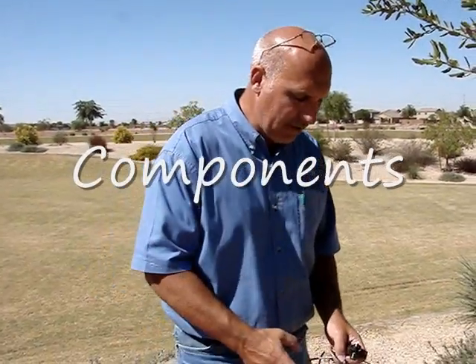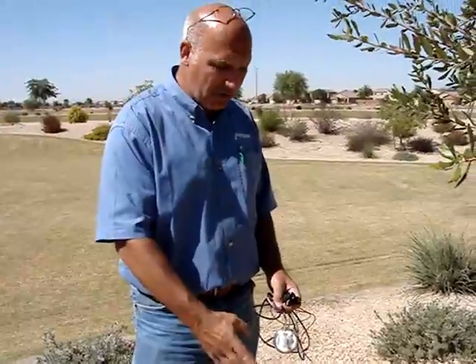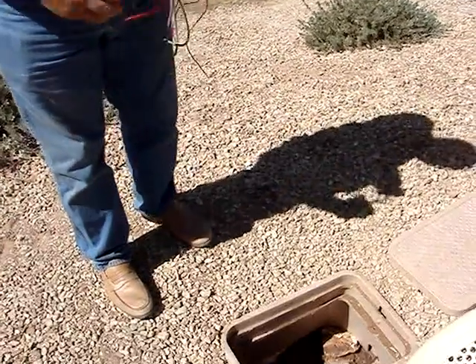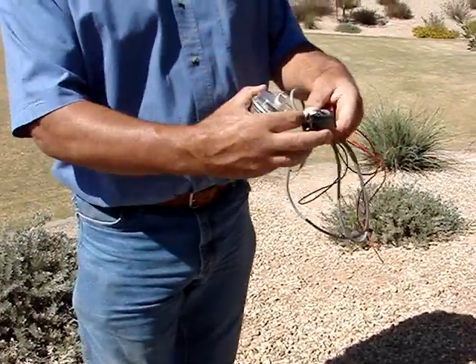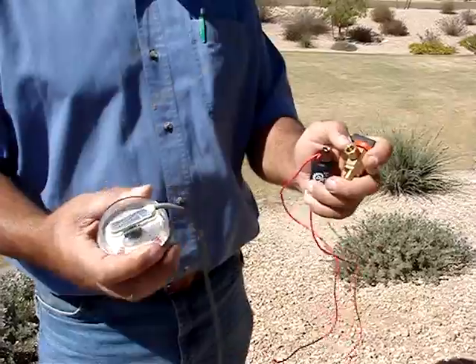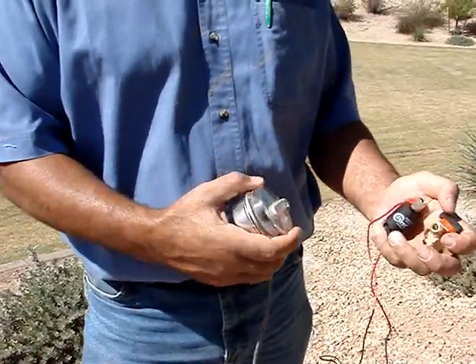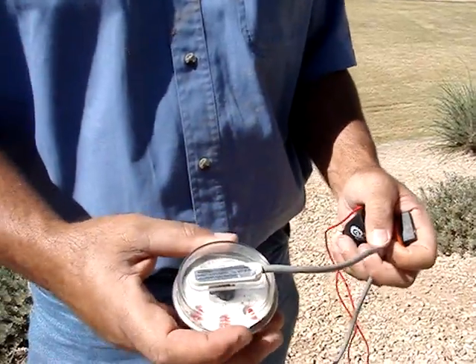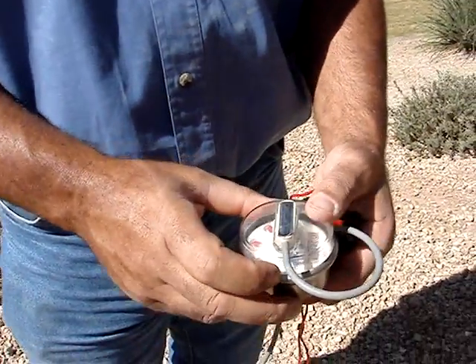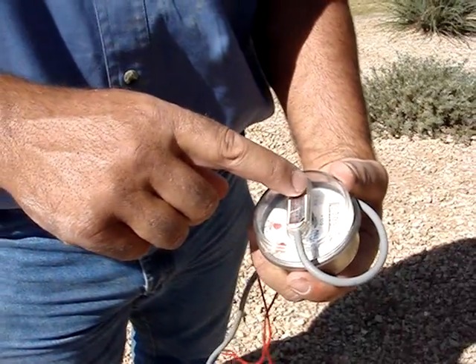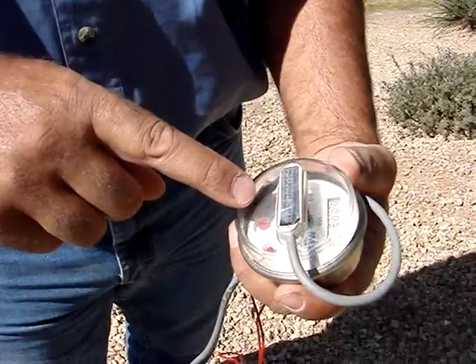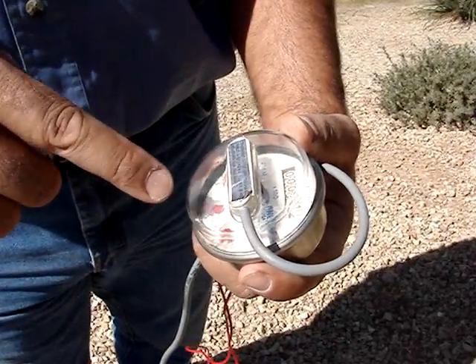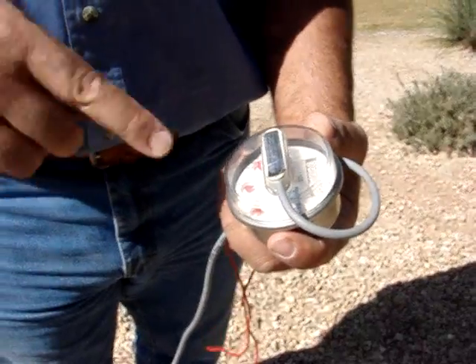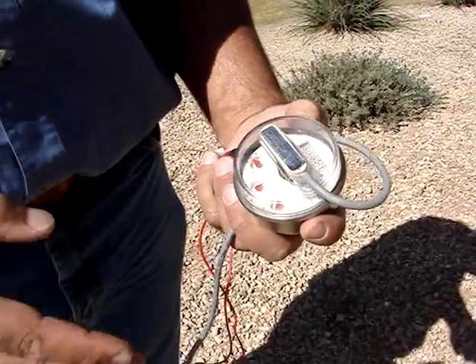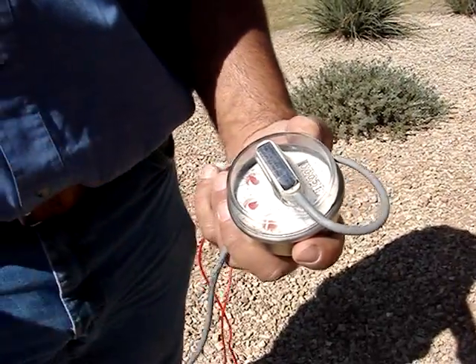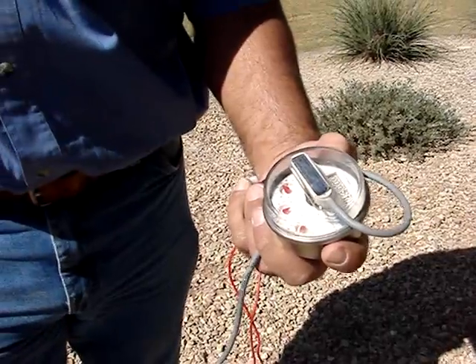Okay, now I'm going to talk a little bit about the hydrometer itself. This one happens to be a 2-inch unit on this installation. The major components are the register, the solenoid, and the 3-way selector. Some of the advantages of the 3-way selector and the solenoid I'm going to explain in just a minute. First of all, the register. One nice thing about this is the register has a non-volatile record of all the water that's gone through the meter ever since it was installed. The other thing is that when you're comparing the flow rate to the clock, the dials are moving, so it's easy to tell whether water is flowing through and also how much, so you can make sure that you have your K factor and offset set correctly.